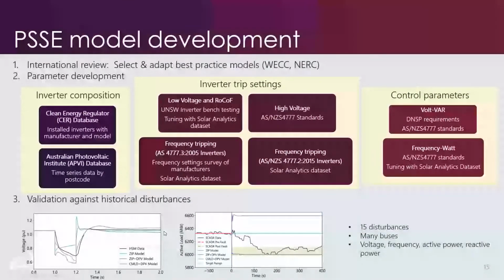This is showing some high-speed data measured at a particular location for a particular historical fault. The actual data recorded is in black. The old model that we've been using is in light blue, which is producing this very fast recovery and this big spike. The newer model that we've been developing is in purple, and you can see it's showing a much better representation of the slower recovery that we see, although with a little bit of overshoot happening.